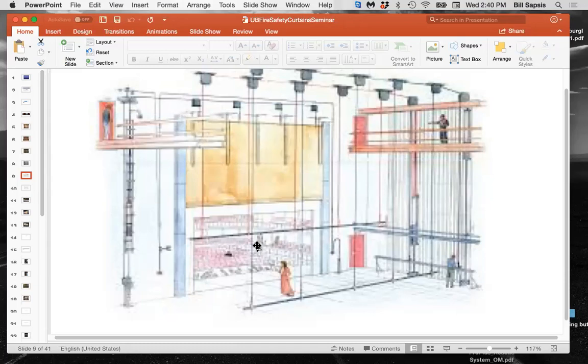which is why I don't think that a deluge curtain is really going to work, because I don't think the water is going to be strong enough to resist that 2 pounds of pressure pushing up against it. But that does speak to the fact that the only thing really holding your fire curtain in place are these smoke pockets. So they are not just tracks. They are a resistance device. They are holding that fire curtain in place should that much pressure be pushed against it.